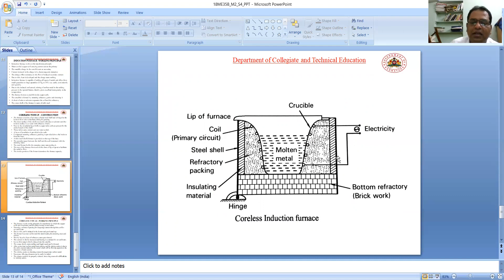The furnace works on the principle of a transformer in which the copper coil is the primary and the charge is the secondary. Sintering consists of passing low ampere current through the coil for several hours. Due to this, EMF is induced in the former and it gets heated up. The former becomes red hot and this starts heating the ramming mass and sinters it. Slowly, layer by layer, the refractory mass gets sintered. The current is slowly increased and heating is continued for several hours.